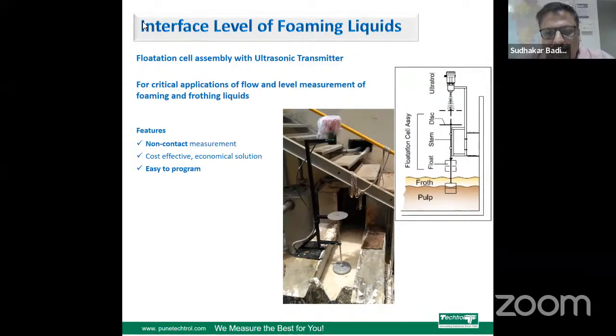And at the other end, with the stem connection, there is one SS plate, as shown. So this movement of the float and the corresponding SS plate movement is detected by the ultrasonic level transmitter. And this can be used as a level transmitter, as well as giving the head height for open channel flow measurement also. So this is one example we did in one government company.